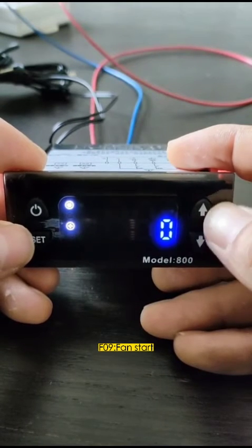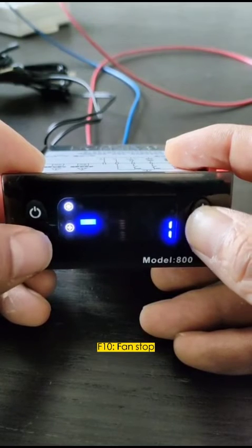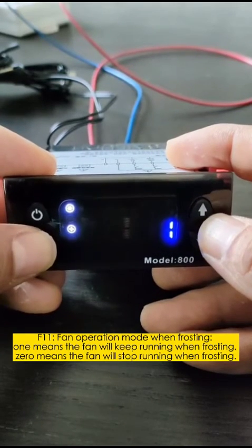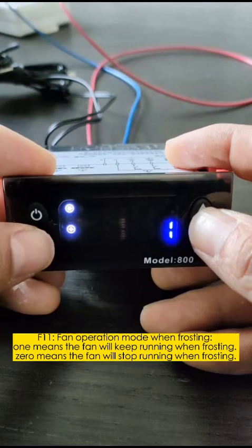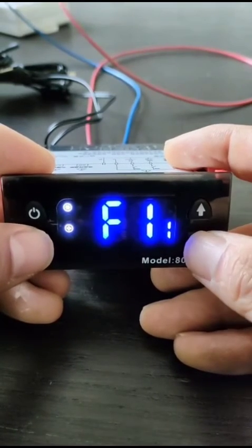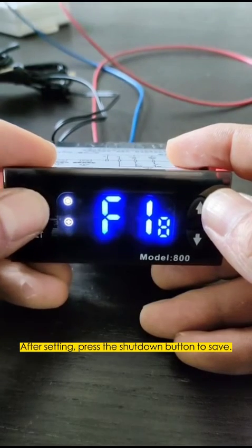F09: Fan start. F10: Fan stop. F11: Fan operation mode when frosting — one means the fan will keep running when frosting; zero means the fan will stop running when frosting. After setting all parameters, press the shutdown button to save.